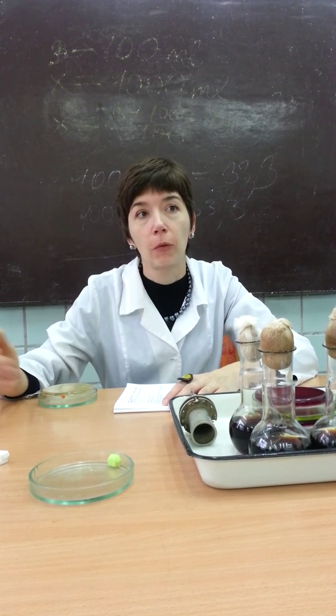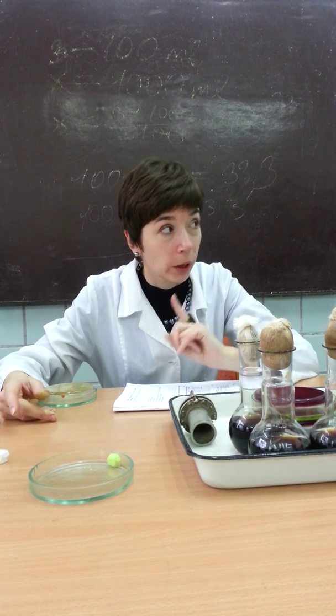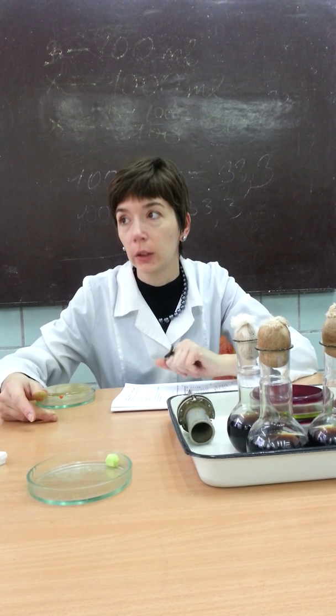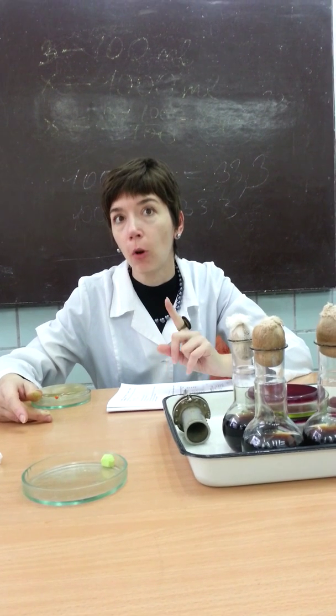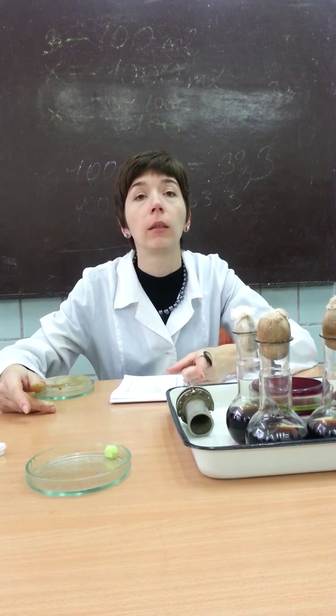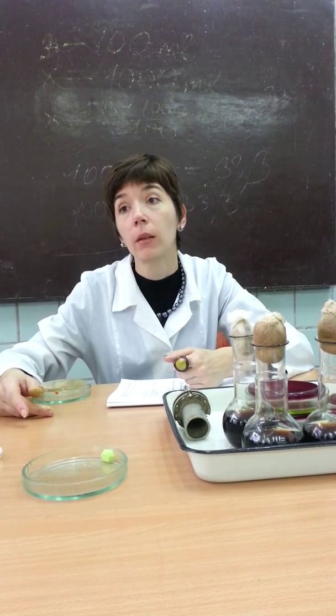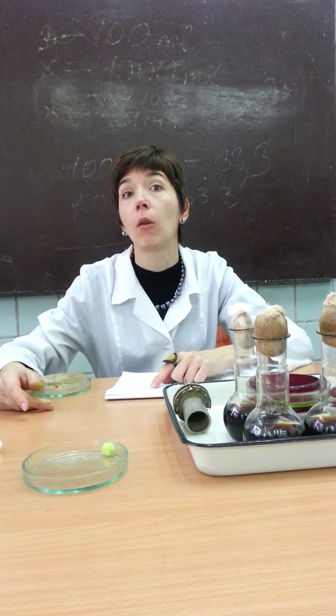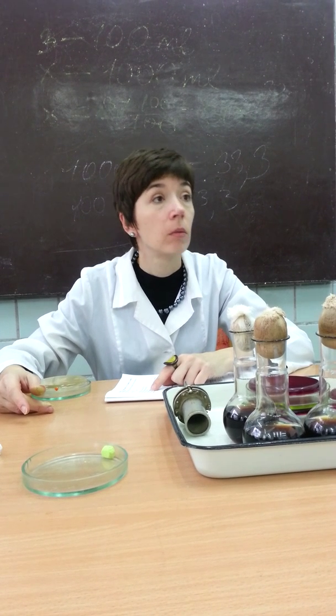The total microbial number for an operating room before operation must be less than 100. After operation, maybe about 1,000. In operating rooms Staphylococcus aureus, Enterobacteria, Candida, and other pathogenic bacteria must be absent. Non-pathogenic may be present, but not more than 100.